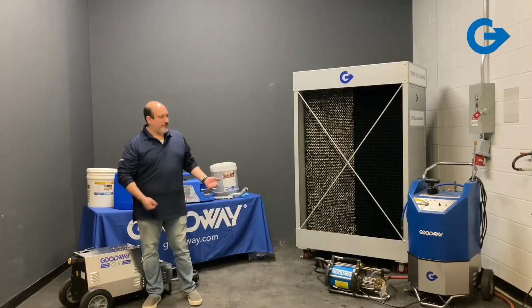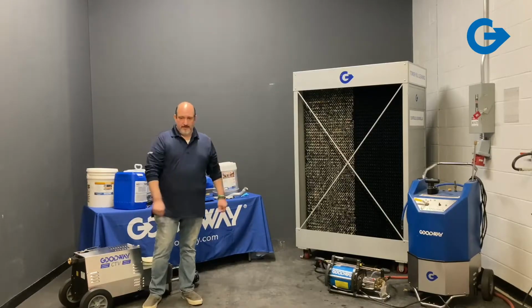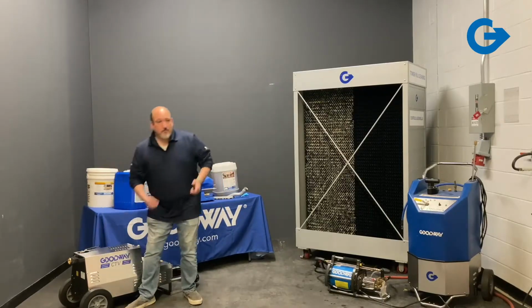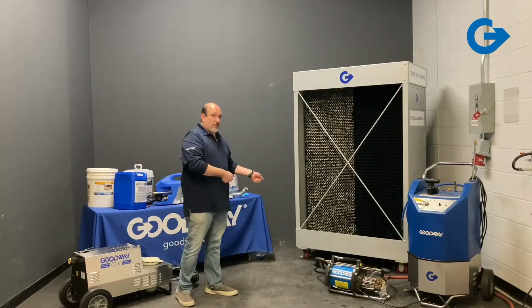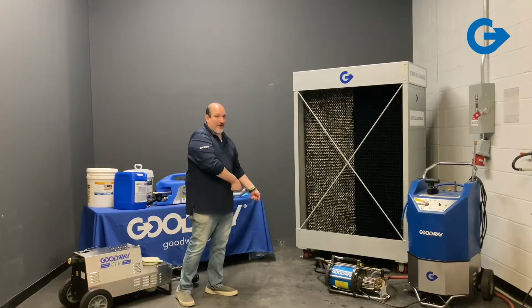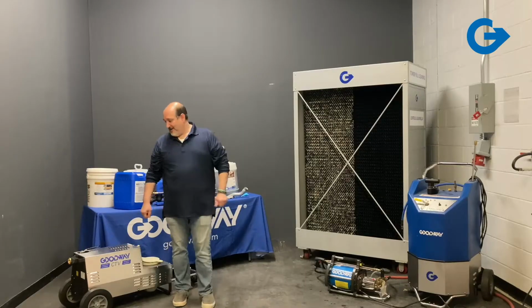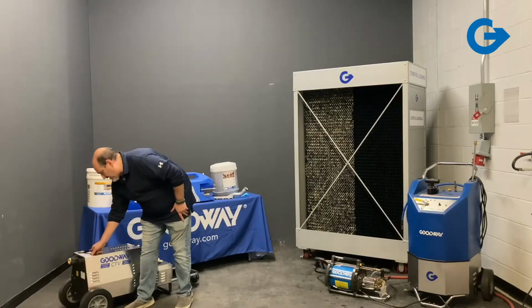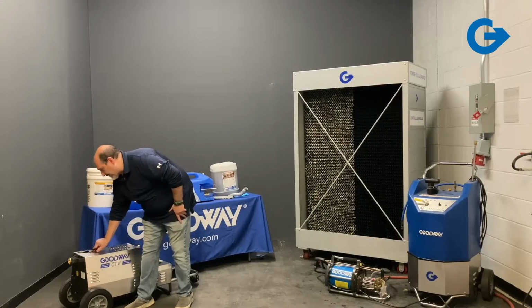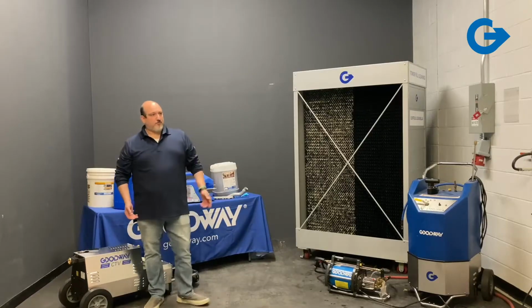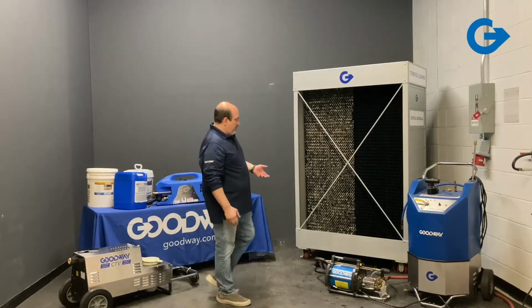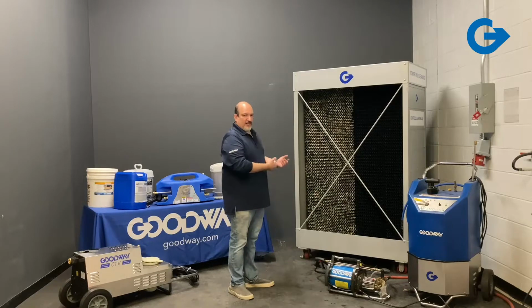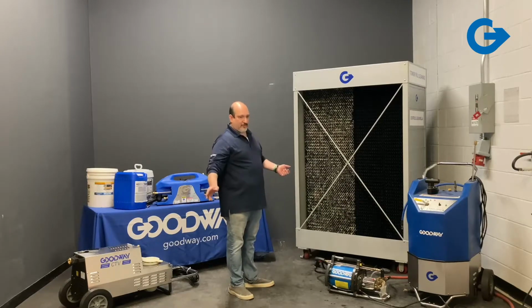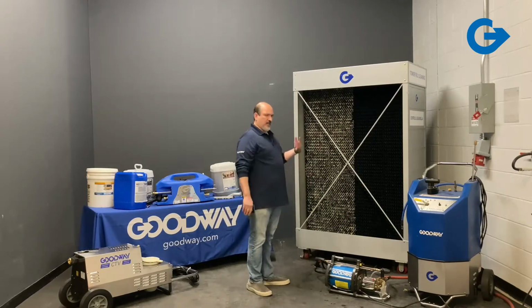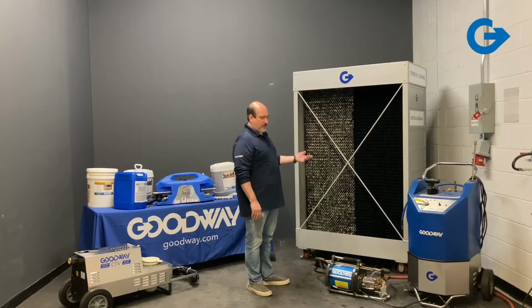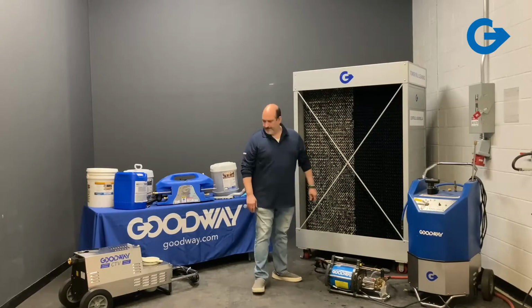You're not trying to drain your tower, you're just trying to vacuum it. If I turned it all the way up, most tools that I would use when vacuuming would be sucked right to the floor of the tower. You wouldn't even be able to use it comfortably. So what we'll do is open it, usually somewhere around a third of the way, so it's around 20 GPM. It's just pulling enough water out of the tower to dilute that sludge that's in there and allow it to pass through without draining down your tower. Your makeup will keep up with the amount of water that you're vacuuming.